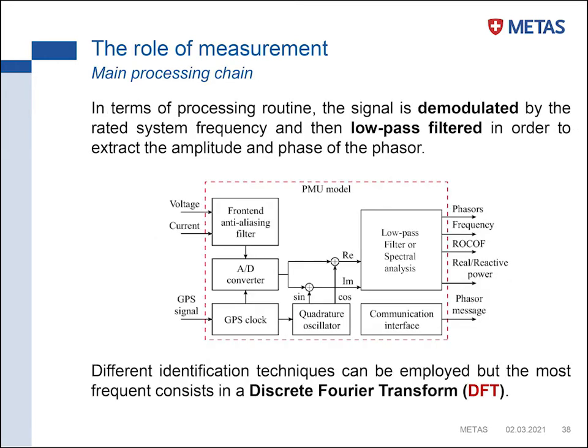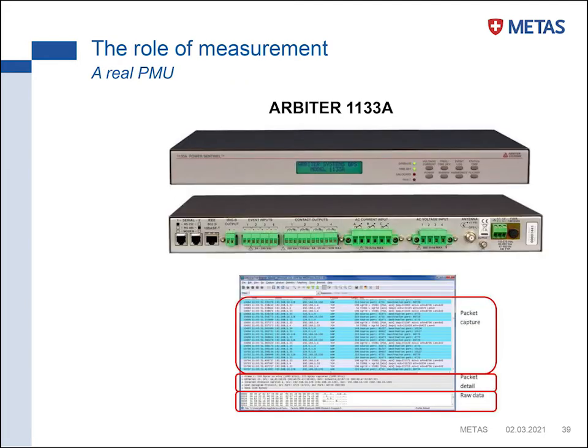Looking more closely at how it works internally, it's quite a simple instrument. First, analog to digital conversion. Then we demodulate the signal by means of a quadrature oscillator around the nominal system frequency, 50 Hertz, and apply some processing — which can be just a low-pass filtering stage, or some spectral analysis, typically based on the discrete Fourier transform.